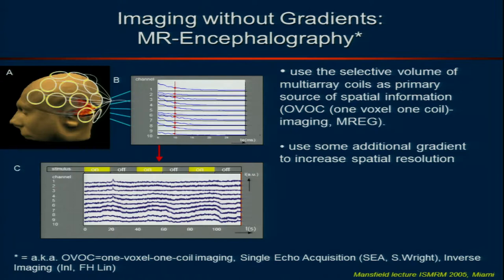It was just an example that imaging speed in MR is limited by gradients. We need gradients to get spatial encoding, but gradients also make everything slow. So if we could do imaging without gradients, we would immediately be infinitely fast. We could sample as fast as our ADC is sampling, so we could acquire images at megahertz rates, but of course with the lousy spatial resolution of basically an EEG scan.